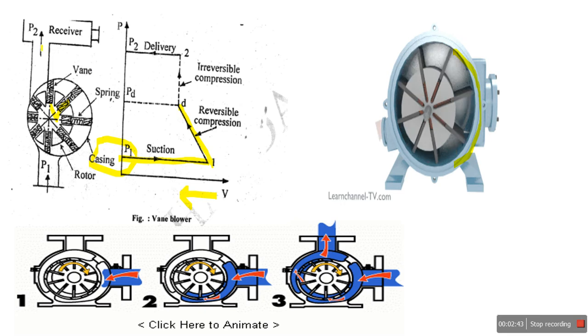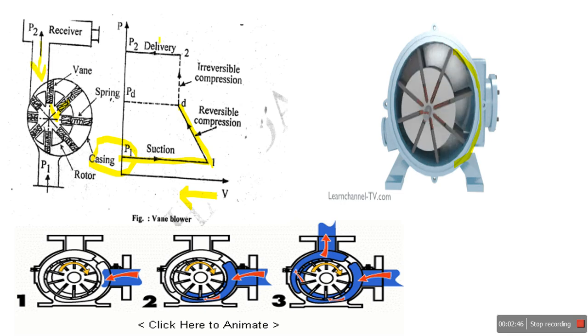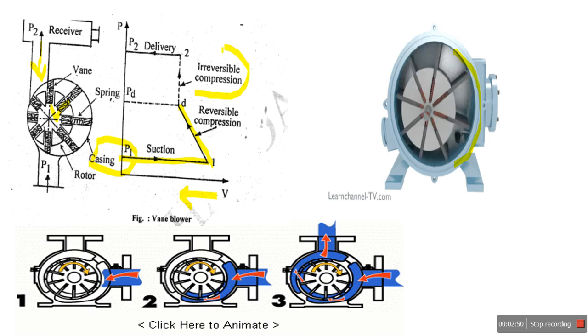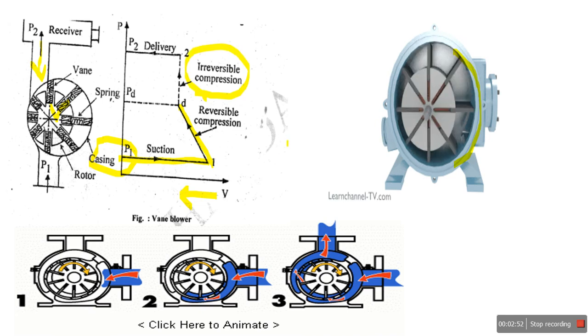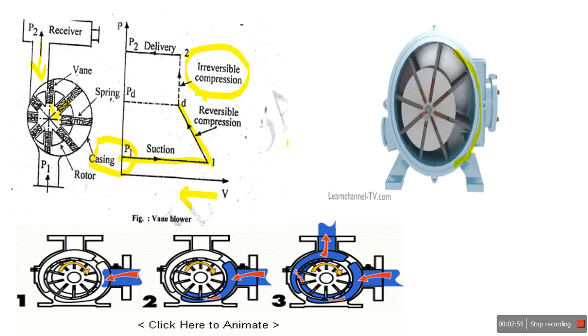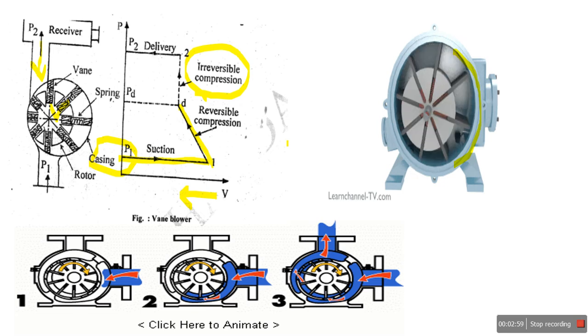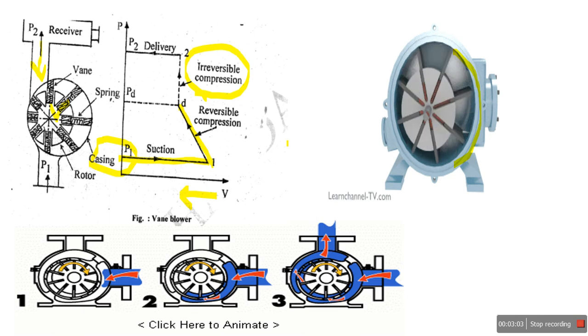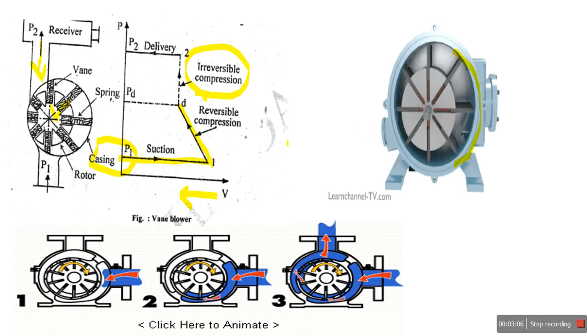Further, the channel opens to the receiver and some air rushes back from the receiver — that is the irreversible compression. So the vane compressor uses a combination of volume reduction and backflow of air. Using these two methods to compress air, this type of compressor requires less work compared to the roots blower for the same capacity and pressure rise.